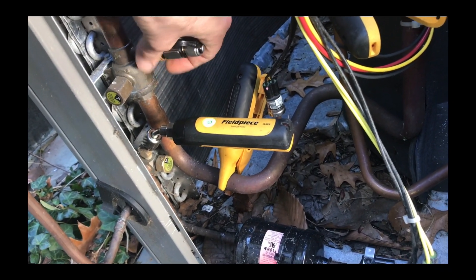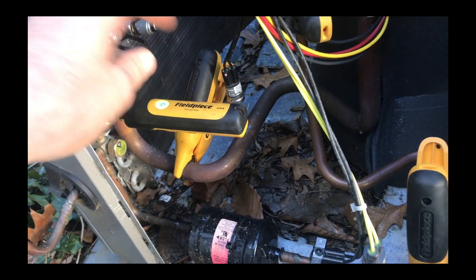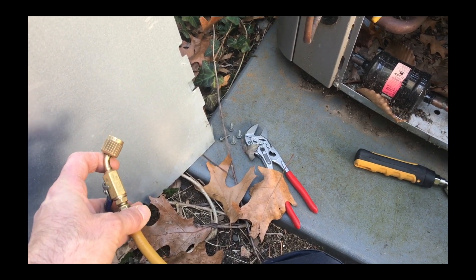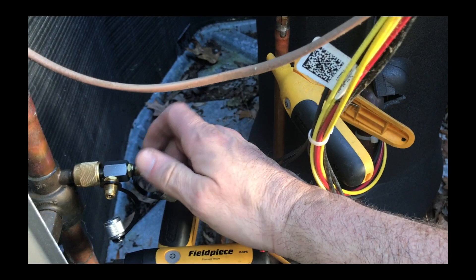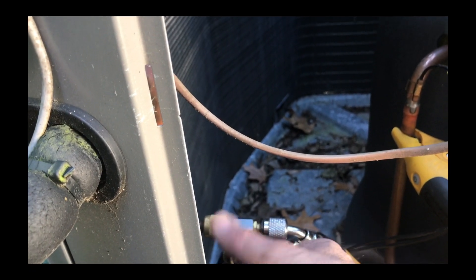So you put this on your suction line, now you open it up. Your hose is going to have to come out of here, so first I'm going to purge the hose — open this up and you open this side. Now you can hook your probe up right here, so now you have access for pressure.